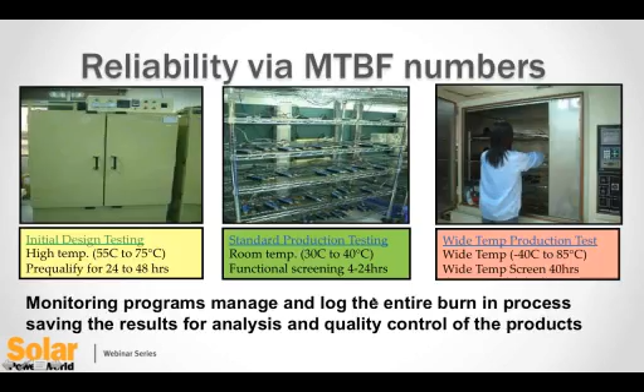As you can see here, this is actually a special heating chamber, but this particular example is a fanless heating and cooling enclosure. It's all radiated heat and cooling, very similar to the enclosures used outdoors, where most of this equipment will likely be installed. That whole process of design testing, running the temperature up and down, is all outlined in many of these IEC numbers, and most of it's gibberish to common folk like you and I.